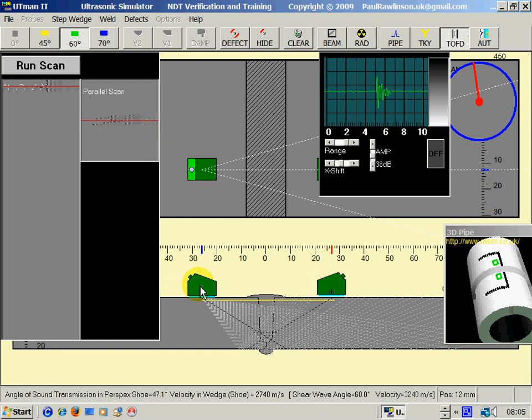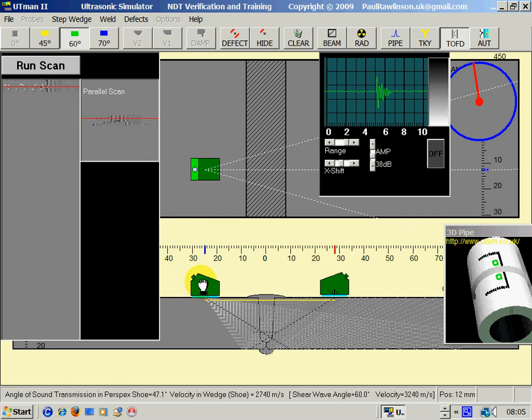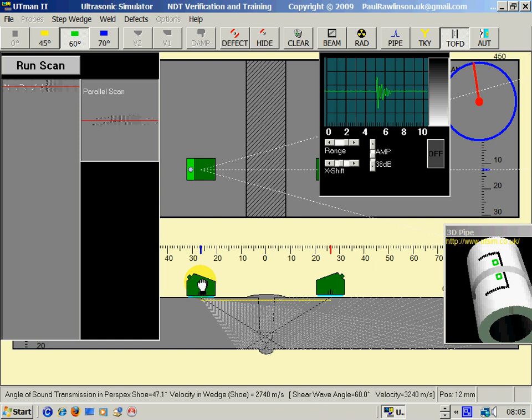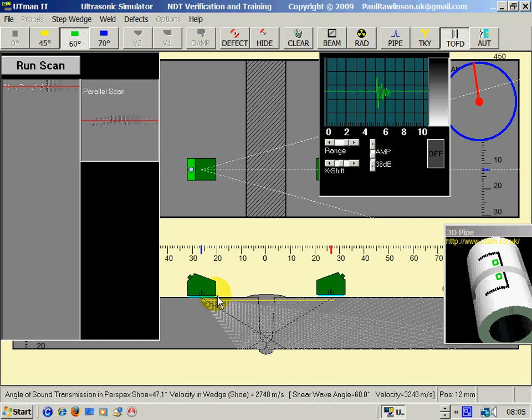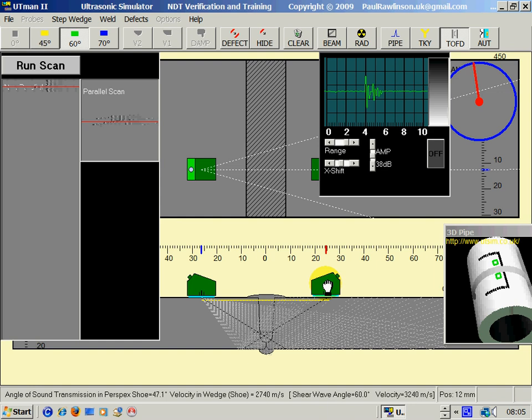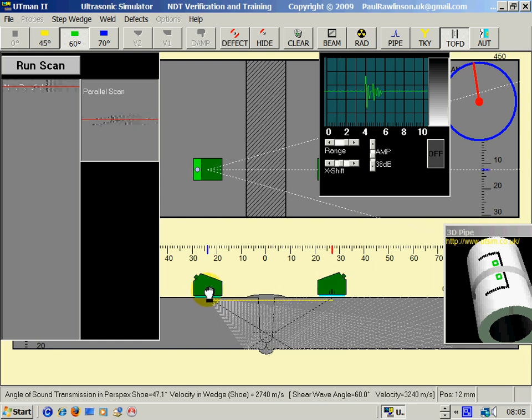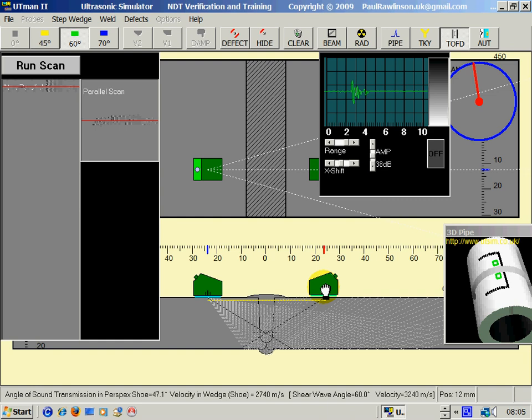We normally set the distance apart so that the center of the beam meets at two-thirds depth. This gives the best response for all weld coverage. You can see the center of the beam is crossing the two-thirds depth line there.